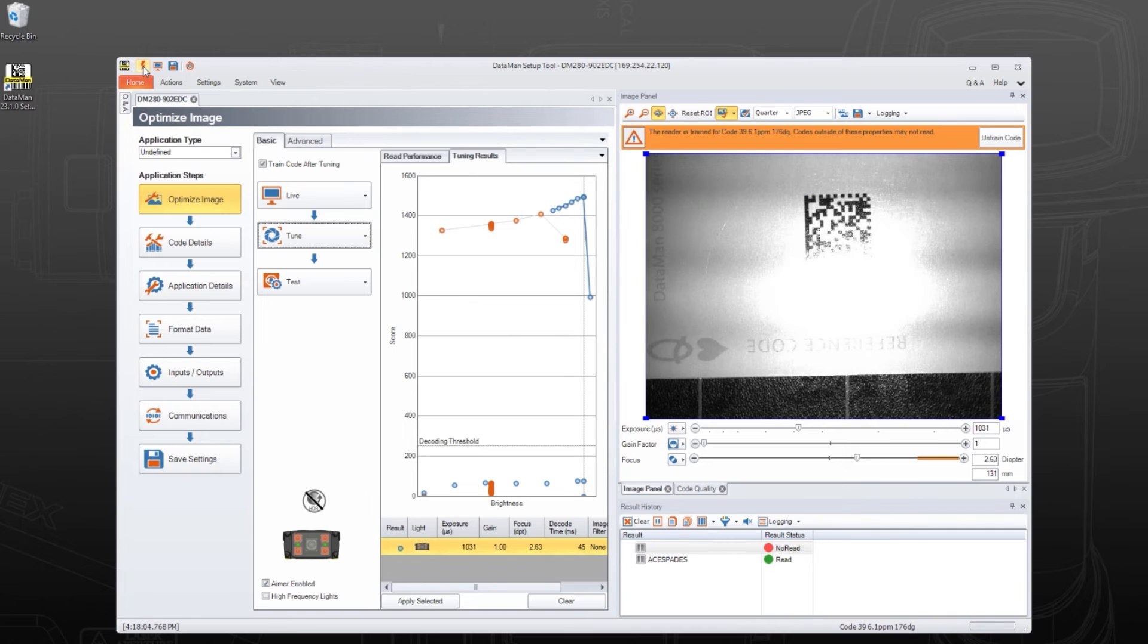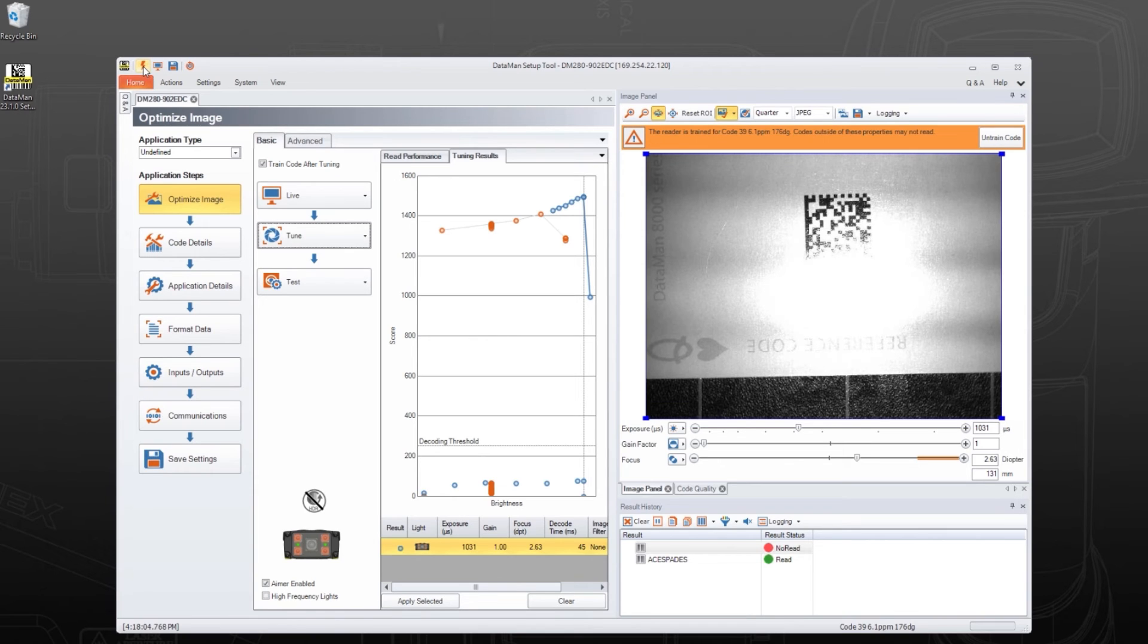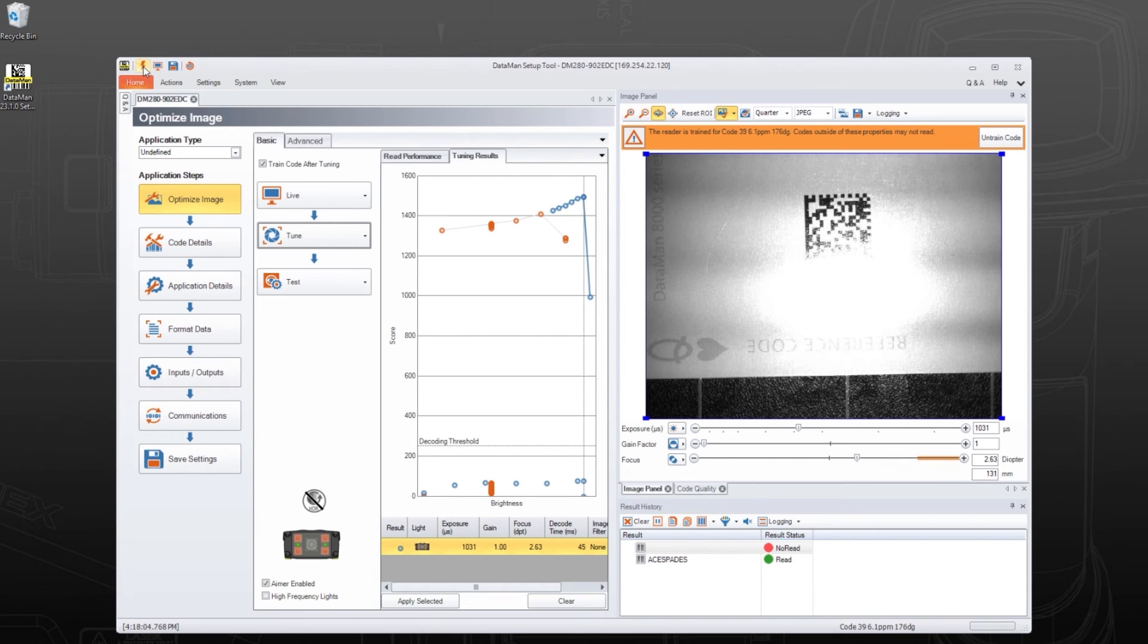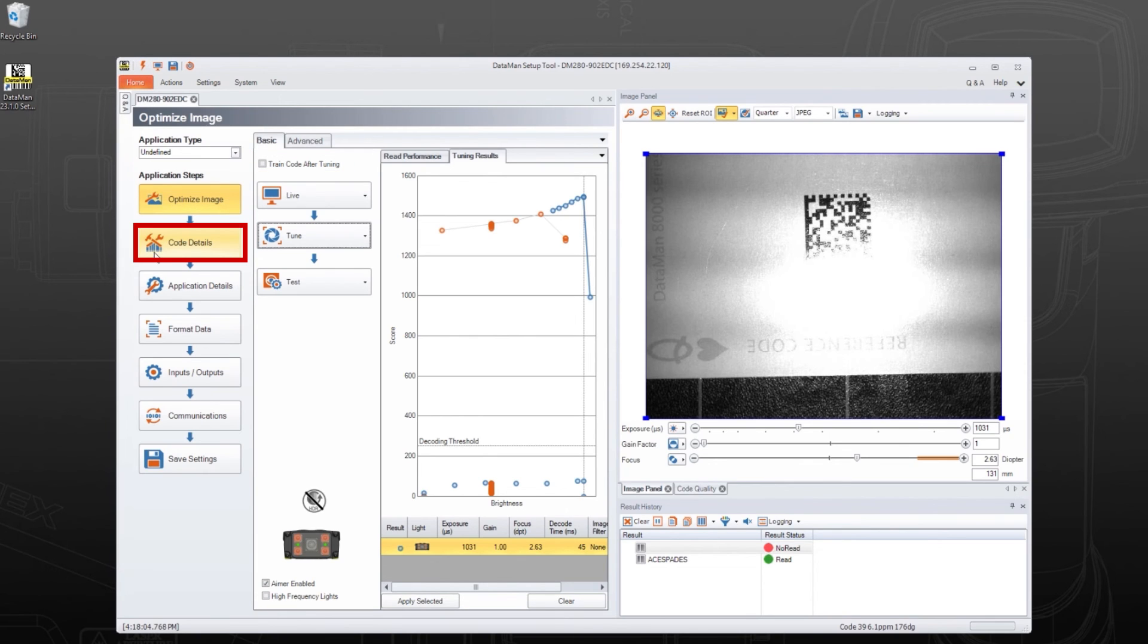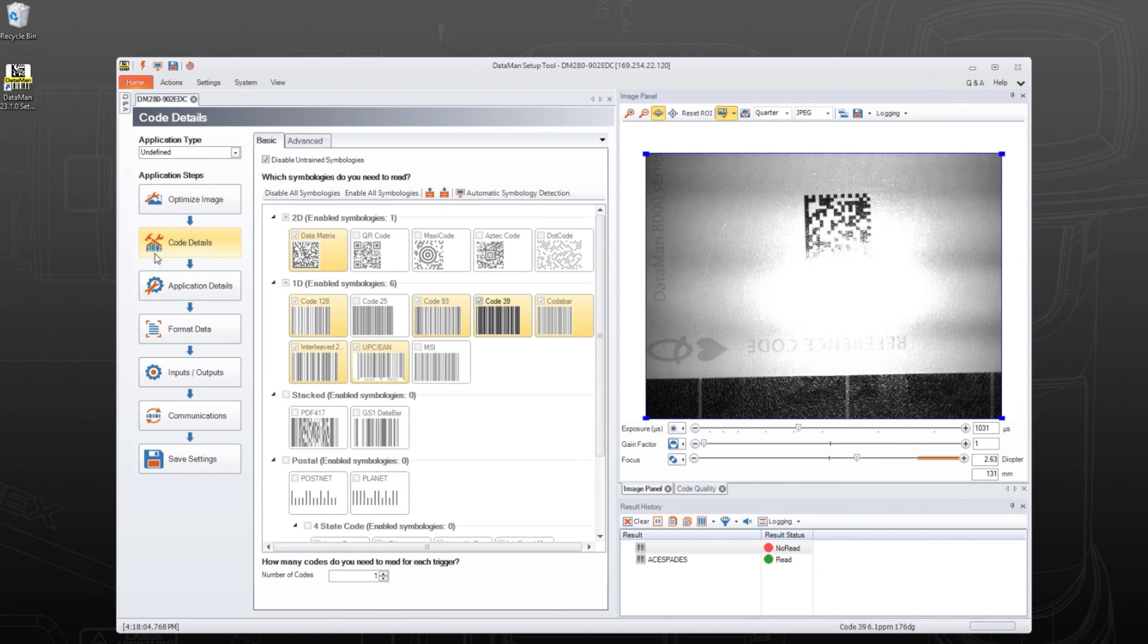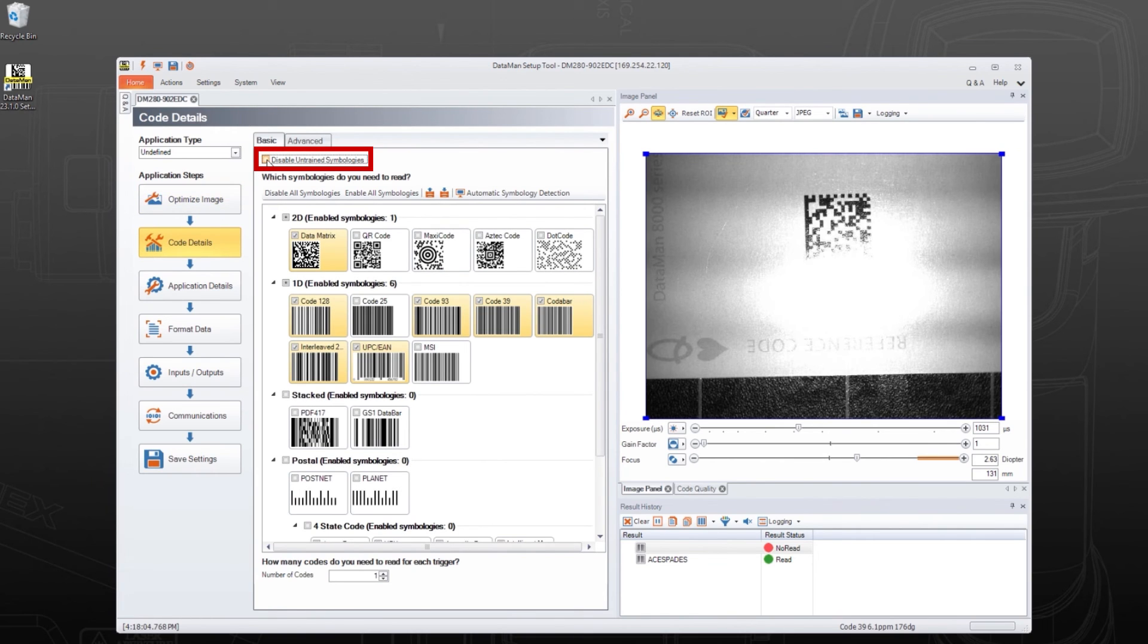If a code is not read, try checking the reader's trained settings. The Dataman setup tool's default settings may train the reader to only read codes with the same size, orientation, and symbology type as the one presented when the reader was tuned. To untrain the previous code, click Untrain Code and uncheck the Train After Tuning checkbox to prevent this from happening again. The symbology settings can be changed in the Code Details application step. Uncheck the Disable Untrained Symbology checkbox and confirm your desired code symbology type is selected.